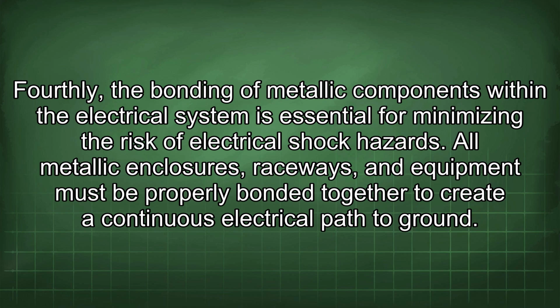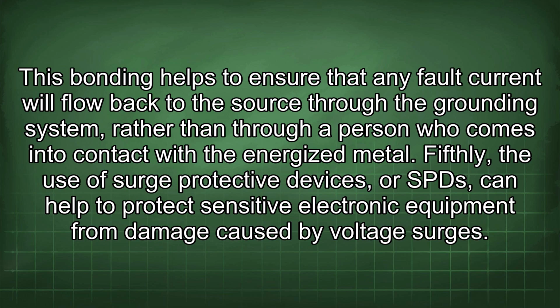Fourthly, the bonding of metallic components within the electrical system is essential for minimizing the risk of electrical shock hazards. All metallic enclosures, raceways, and equipment must be properly bonded together to create a continuous electrical path to ground. This bonding helps to ensure that any fault current will flow back to the source through the grounding system rather than through a person who comes into contact with the energized metal.